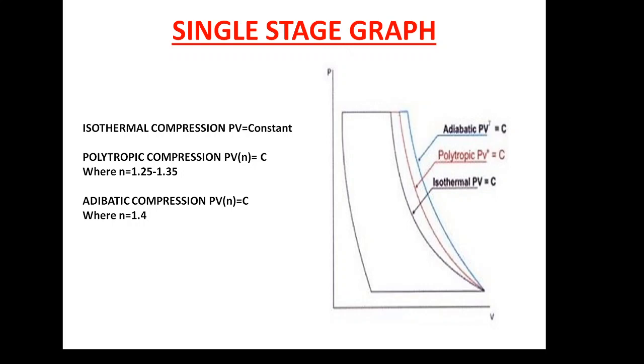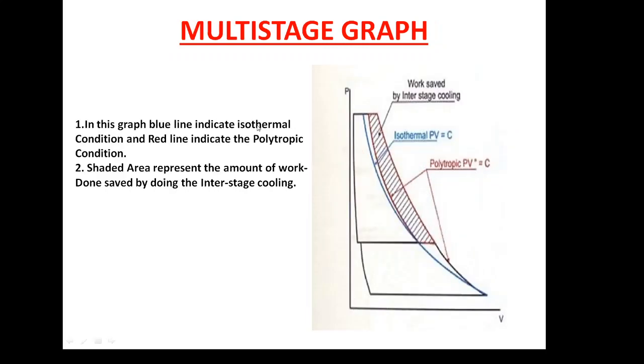Now let's first talk about multi-stage and how it overcomes the problems of single-stage. Let's see the multi-stage graph. In multi-stage, as I have told you in my earlier video about isothermal, polytropic, and adiabatic compression — the polytropic process is the process which basically occurs in a compression cycle. Our main aim is to achieve an isothermal compression graph, because isothermal compression indicates that the amount of work done will be minimum.